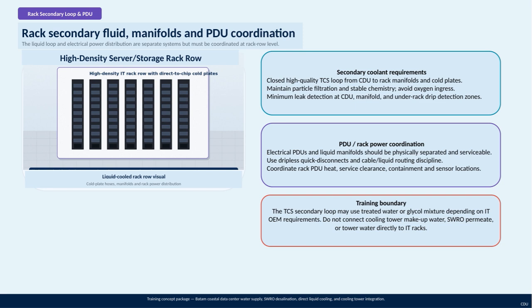When it comes to the power distribution units, they must be physically separated from the liquid manifolds to reduce risk and simplify maintenance. Using dripless quick disconnects and organized cable and hose routing helps ensure safe, clean service access. Additionally, we have to carefully coordinate heat output from the PDUs, ensure adequate service clearance, and properly locate sensors and containment systems. It's important to note that the secondary cooling loop typically uses either treated water or a glycol mixture depending on the specifications of the IT equipment manufacturer.